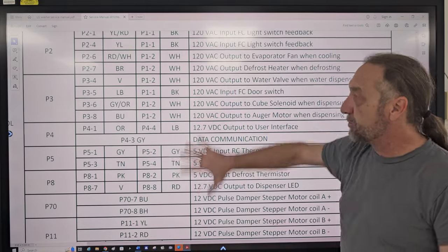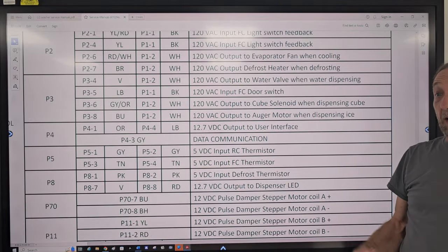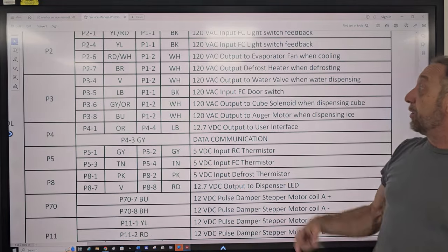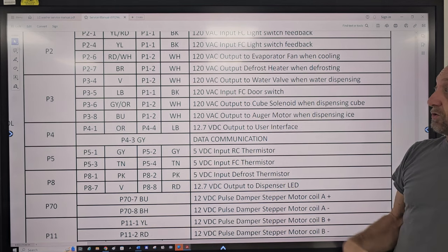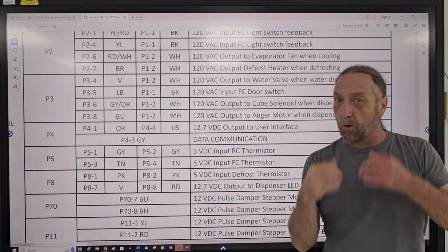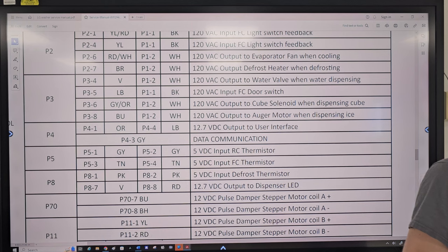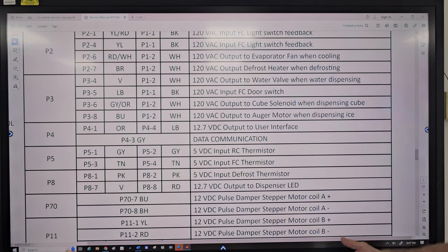So what this matrix on this page is telling you is, hey, you want to check the fan motor, you want to check the water valve, you want to check the door switch, you could check these components right from the board. And it's nice, it tells you where to put your meter, what color wires and where.